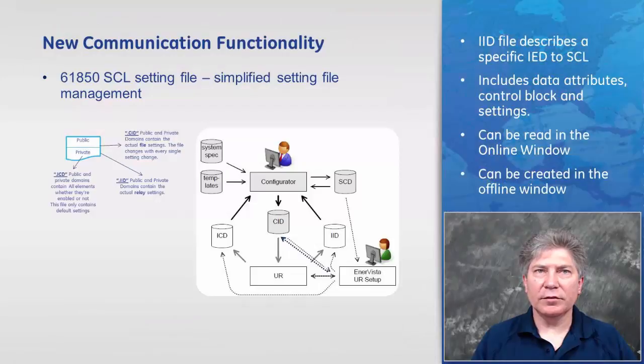The IID file, the Instantiated IED Description file, describes a specific IED to a system configurator tool, typically more or less as configured for its role in a system. The IID file includes the data attributes of the UR device, the control blocks and settings, with all the settings values as they were at the moment that the IID file was generated. A copy of it can be obtained directly from a UR device or from EnerVista UR Setup. The IID files can be read in the online window and created in the offline window.